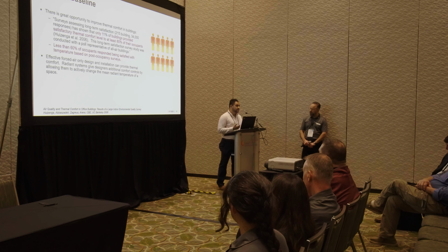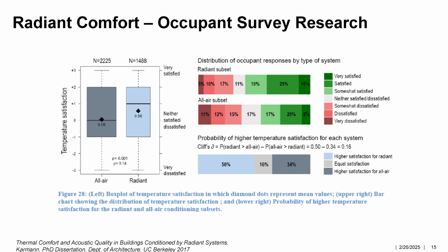So radiant HVAC systems give building designers the ability to control another important parameter for thermal comfort, and that is that radiant systems can control the zone's mean radiant temperature. By having this additional parameter to control, our research suggests that occupants do indeed tend to have higher thermal satisfaction rates compared to conventional all-air systems. These graphs show various analyses of the same occupant survey that I just talked about, showing the increased thermal comfort satisfaction rate when radiant systems were used. So we can say that in a space with a radiant system, a person has a 66% higher chance of having equal or higher thermal satisfaction than in a conventional all-air system.